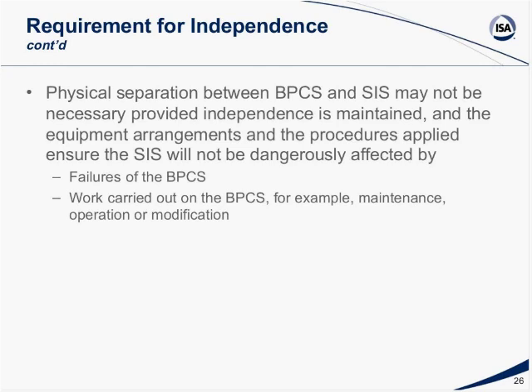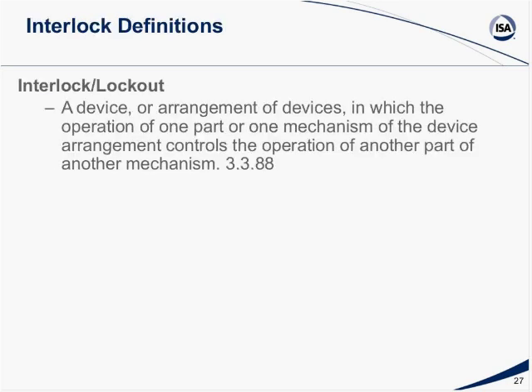Physical separation between control and safety systems may not be necessary, provided independence is maintained and the equipment arrangements and the procedures applied ensure the safety system will not be dangerously affected. It's important to be able to document failures of the control system and work carried out on the control system, for example, maintenance or operation. Any work on the control system will not affect the safety system, or safety management system, or the burner management system, whenever it's defined. So all this is controlled by interlocks, a device or arrangement of devices in which the operation of one part or one mechanism of the device arrangement controls the operation of any part of another mechanism. In other words, if one of these devices should sense a fault, it would go to a safe state or to a shutdown state. And typically, fail-safe is considered de-energized the trip.